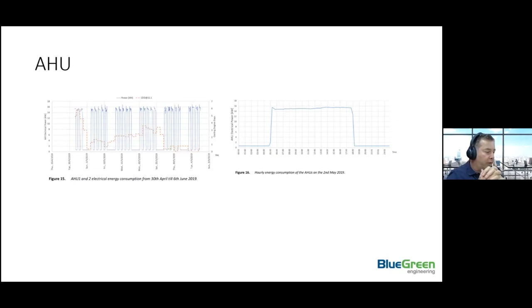This was in wintertime, around May, close to winter. It would bring in cold water and cold air at 5 a.m. in the morning, which would cool the building down, and then the system had to reheat the building before the occupants came through. So the controls were fighting each other. Next slide, please, Stephen.